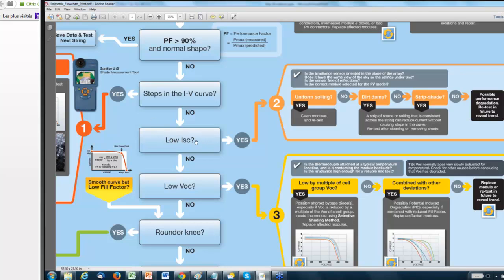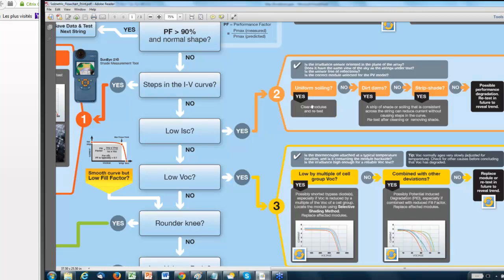So if you have a low ISC compared to the prediction, that's case number 2 in the deviations, and so you go into the orange block. The first thing you check is to see if you have uniform soiling on the array, because that is just like not having enough light. If you are nice and clean, at least you don't have the broad film, uniform film of dirt, then you say no to that box and you go to the right and check to see if you have dirt dams or strip shade. And these are abbreviations because of space, but what that means is either you possibly have a collection of dirt at the bottom edge of the module, or there's a strip of shade at the bottom edge of the modules cast by another row of modules, or cast by a parapet wall, or a railing or something like that.